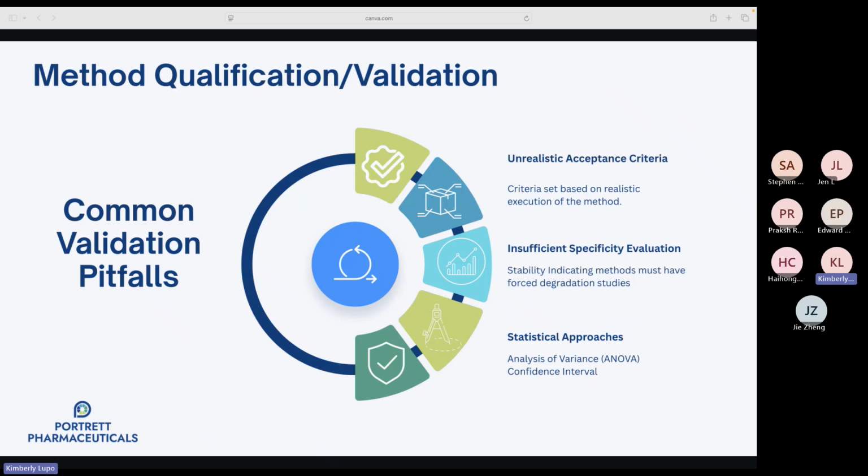And for intermediate precision, you need to incorporate the sources of variability that will be present in routine use. So different analysts, different days, different instruments, or lots of columns and reagents. A common design is 2 analysts, 2 days, 2 preparations per analyst per day. That gives you 8 measurements that capture realistic variability. Then you use analysis of variance to partition the variance and understand how much is coming from each source.